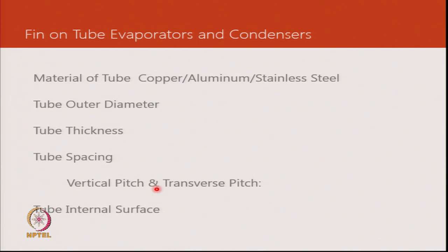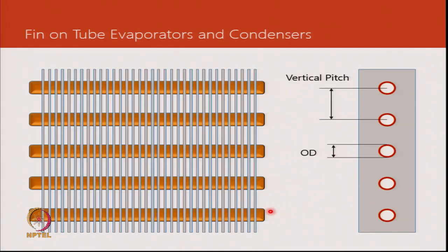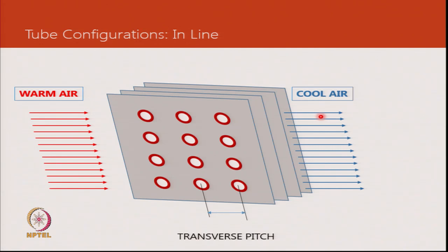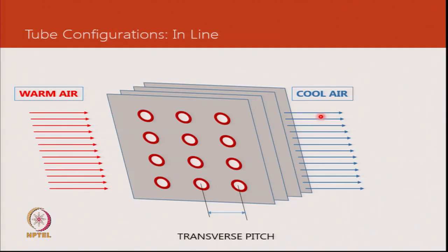In a fin-on-tube heat exchanger, the copper-coloured elements are the tubes and the grey elements are the fins. The variables to define include the number of tubes, the OD of the tube, and the vertical pitch of the tubes. In an evaporator, warm air contacts the cold fin and tube surfaces and leaves at around 12°C with relative humidity in the region of 95% due to condensation.